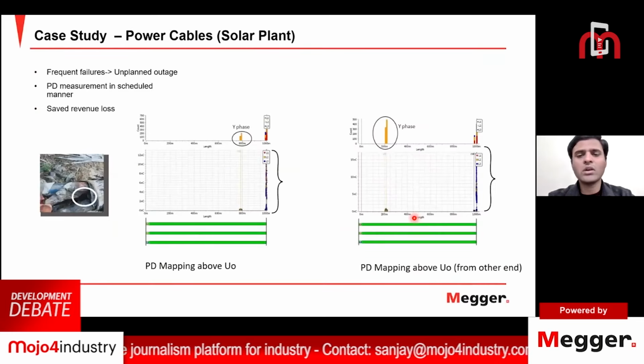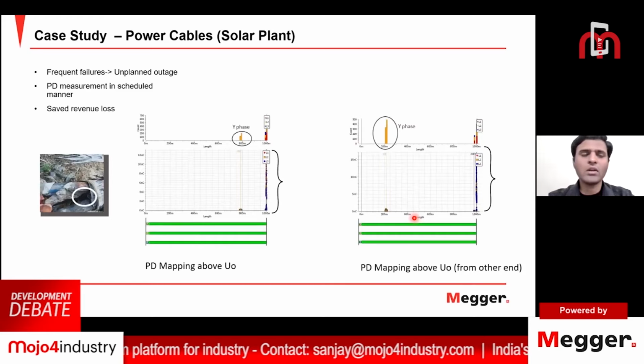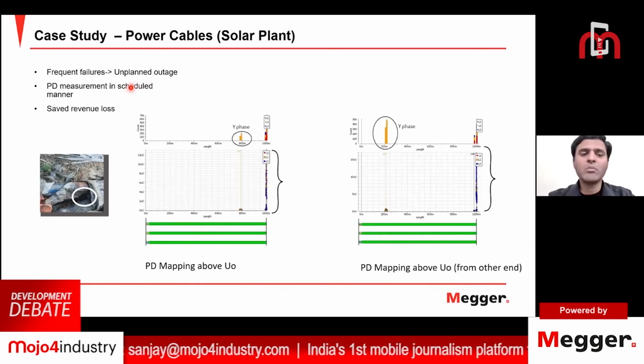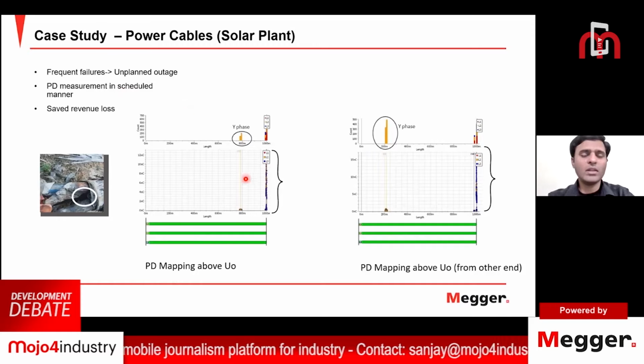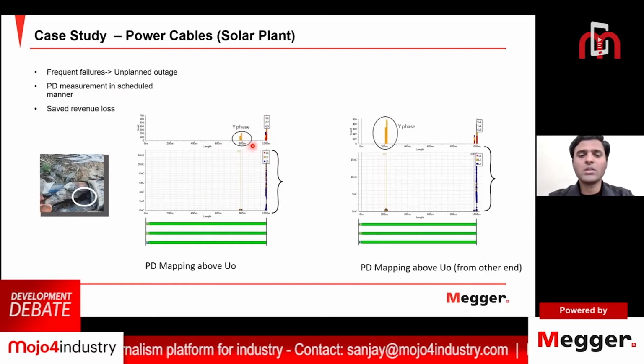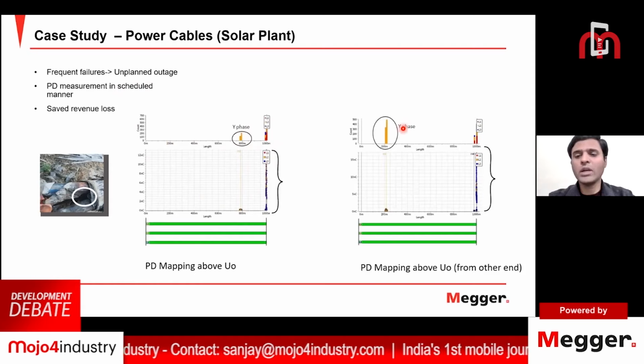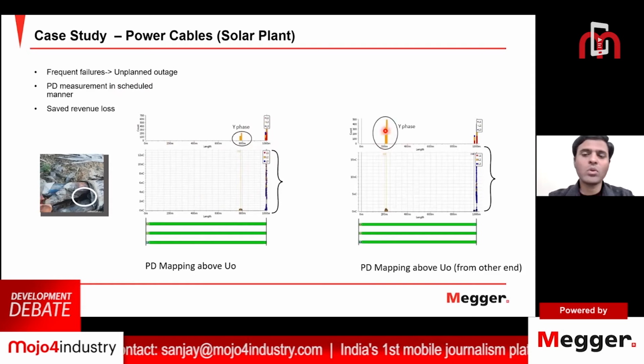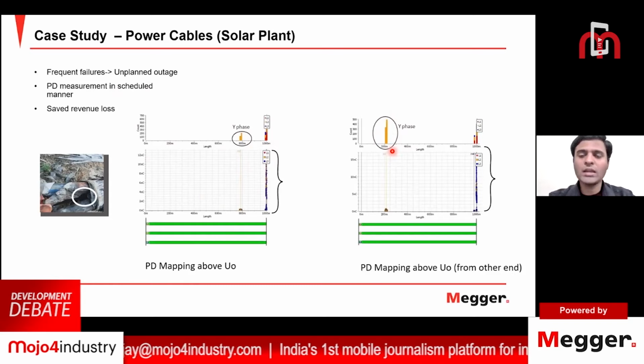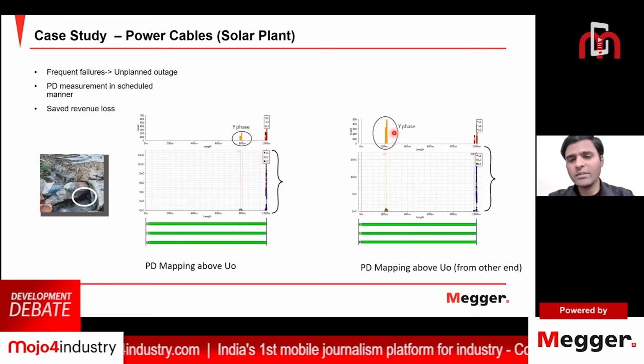This case study is based on a solar power plant where a number of power cables were taken into shutdown and pre-planned predictive maintenance was carried out. A tan delta measurement was done, and also a partial discharge measurement. In one of the cables, it was identified that there is a discharge at about 800 meters along the length of the 1 kilometer cable from the test end, and it was reconfirmed by doing the testing from the other end.